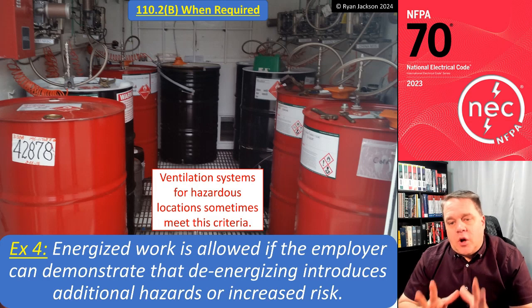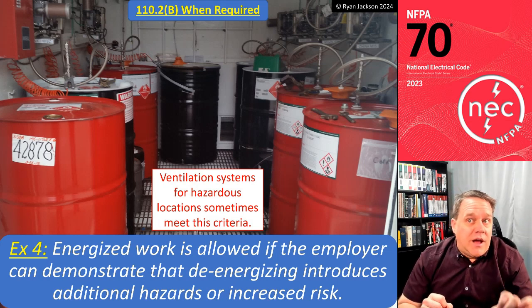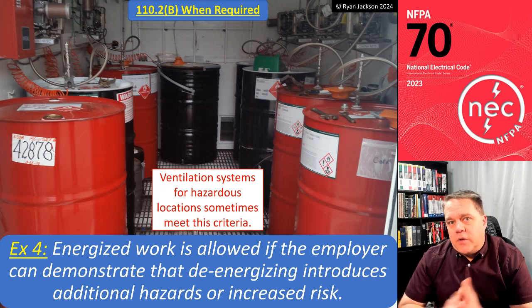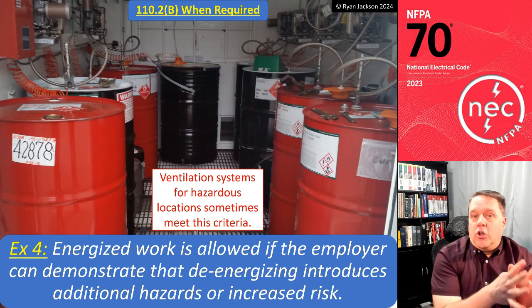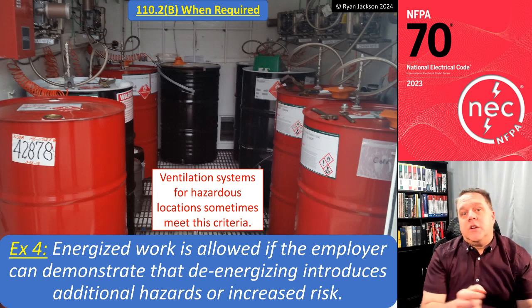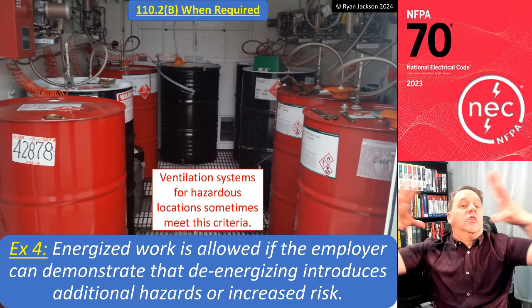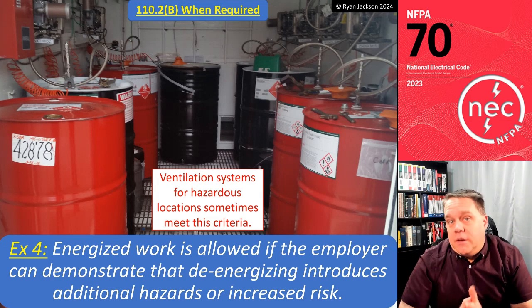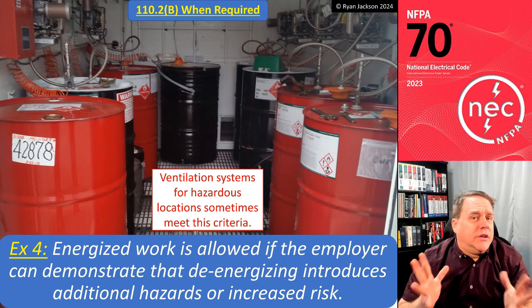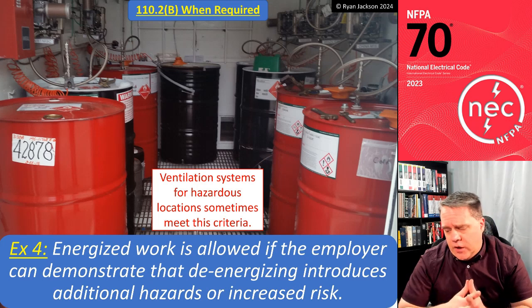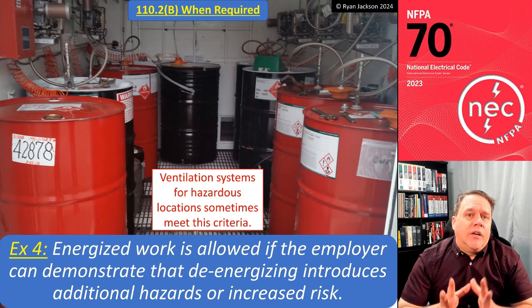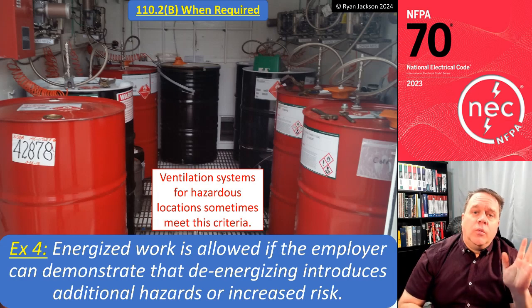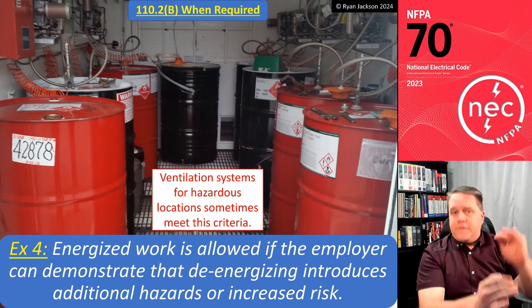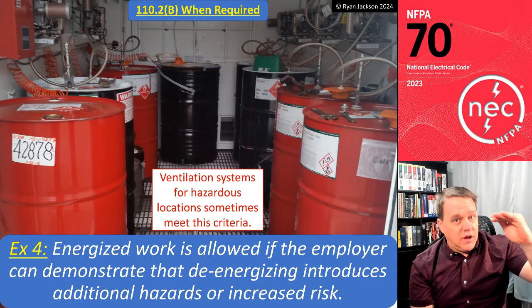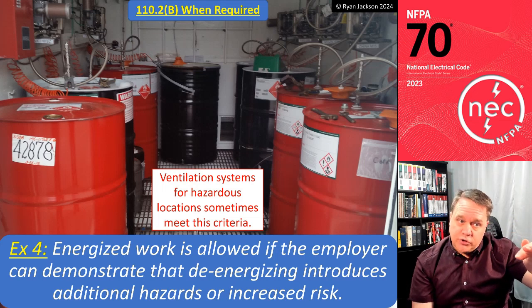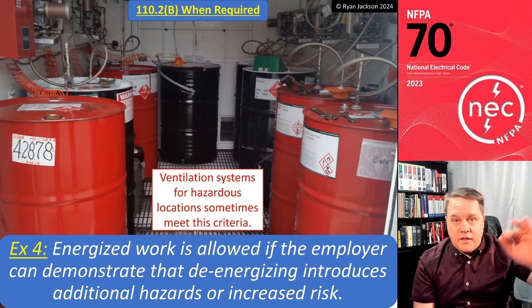But maybe shutting off the ventilation system would create additional hazards, right? So which is a greater hazard? Me getting shocked by working on the ventilation system, or me shutting off the ventilation system and creating an accumulation of ignitable vapors that could then blow up? It's something that the employer is going to have to weigh out and figure out, okay, which is a greater hazard? And if the hazard of shutting it off is greater than you working on it energized, well, then you can work on it energized if you go through the hierarchy of risk, right? See if you can substitute it to a lower risk, see if you can use engineering controls, awareness, all of those things, right? And then down to PPE.